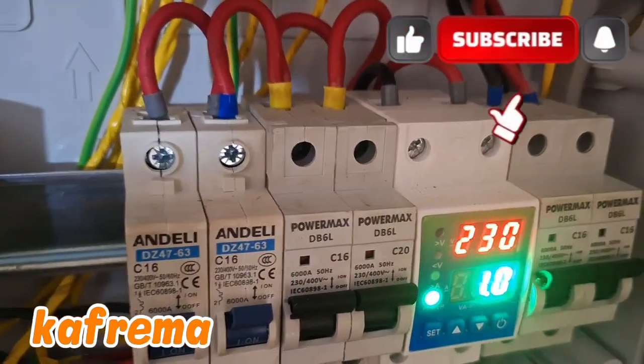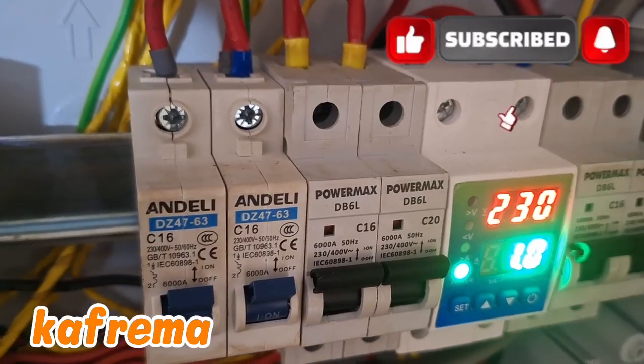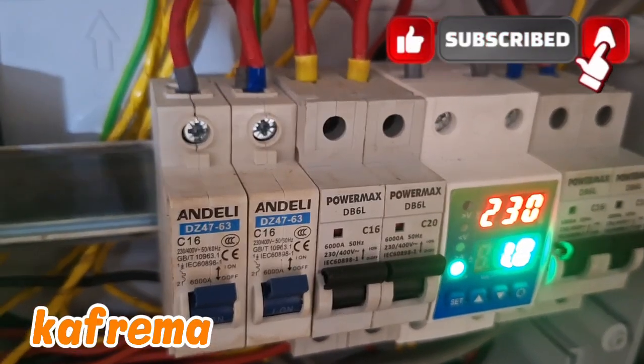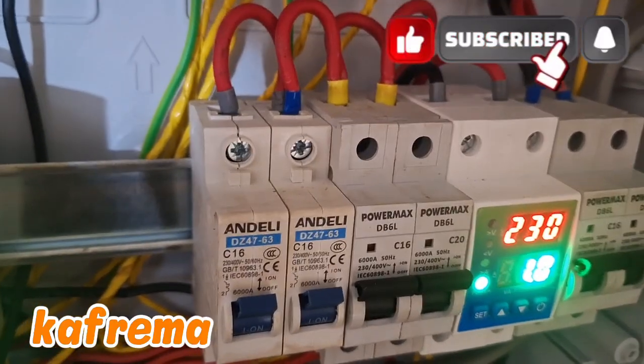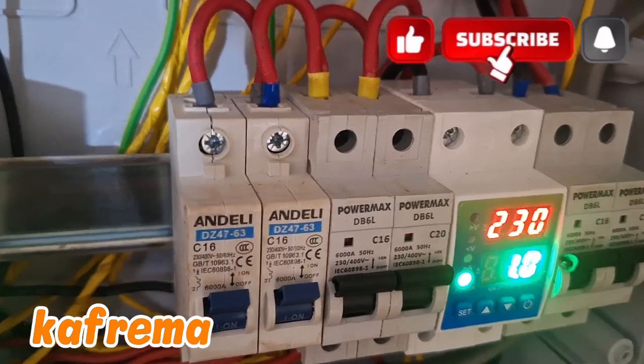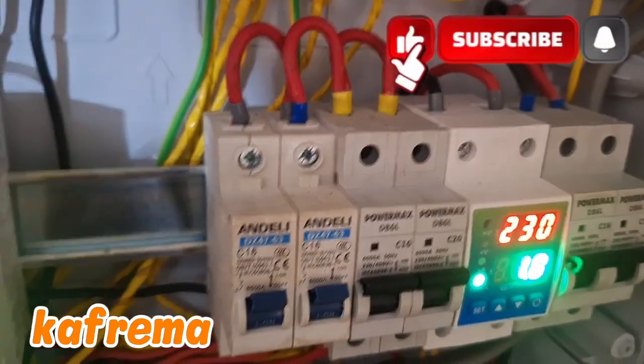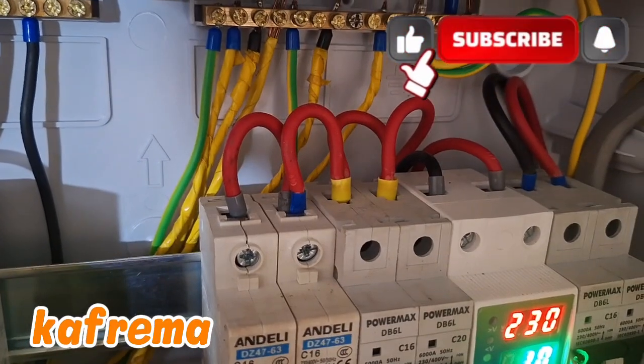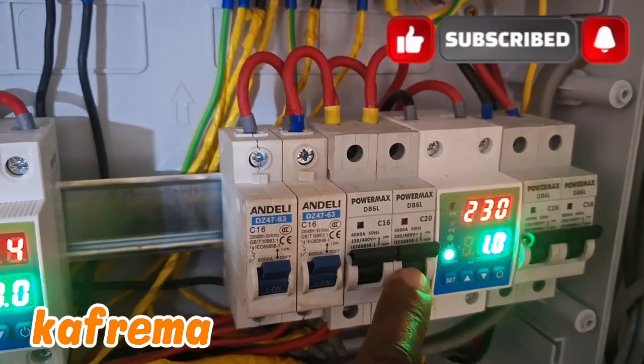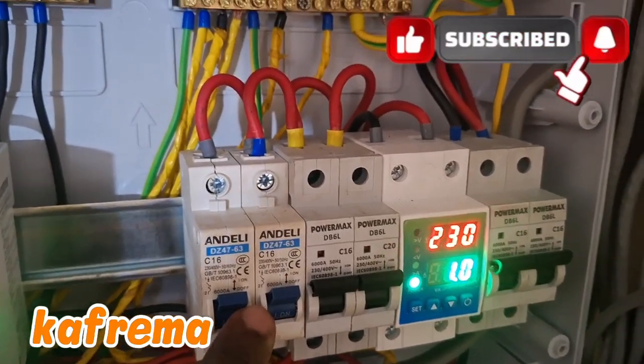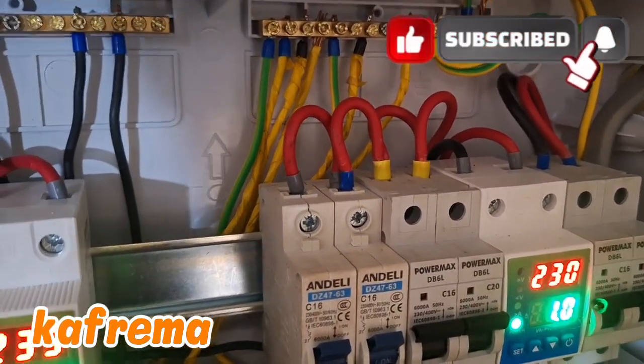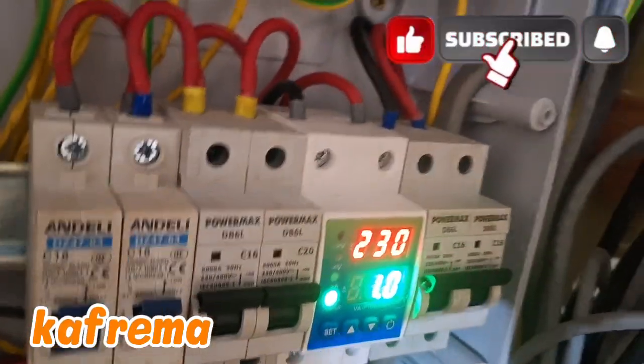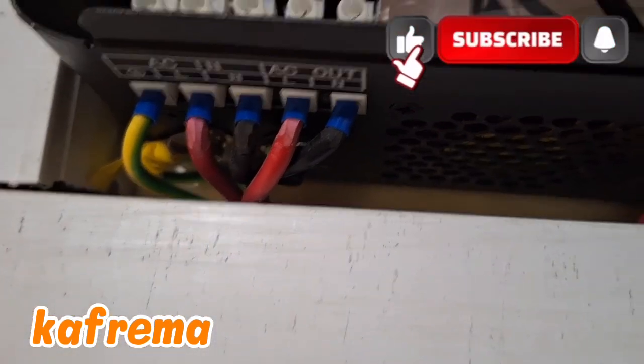So this one protects your load, and also protects your inverter from a load short circuit or overdrawing. Also it will protect your load from the inverter in case your inverter is damaged and produces a lot of current; that power will not get to your items. So these are providing power to different items in the system, like the lights, the fridge, whatever item you want. This is AC power now. Output is AC. From our inverter, we are getting AC out. This is our output, which comes here to this AC box.